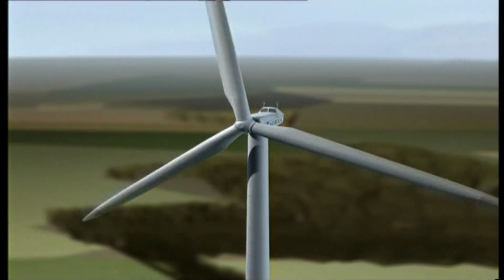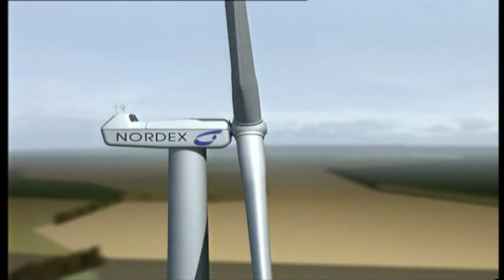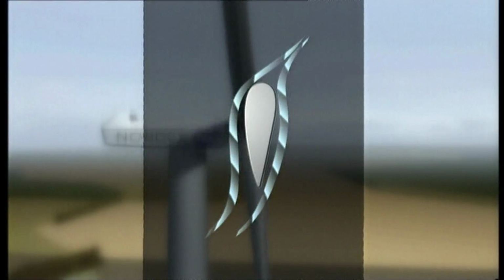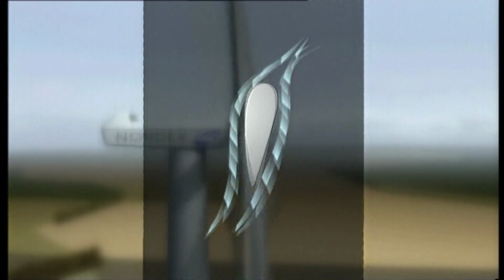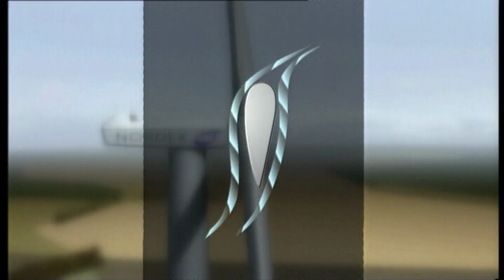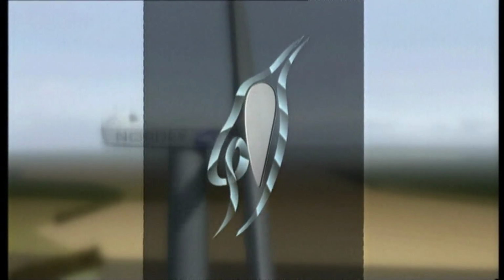When the wind exceeds 15 meters per second, some of the wind must be wasted to avoid an excess load on the turbine. Some wind turbine designs are controlled by turning the entire blade when the wind is too strong. This is called pitch control. Other turbine designs control the pressure on the blade profile by creating a zone of turbulent air at high wind speeds. This is called stall control.